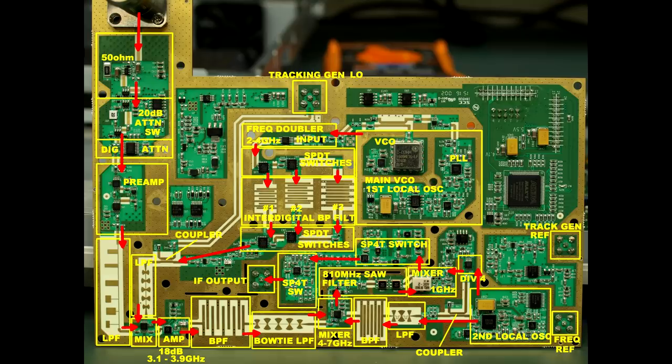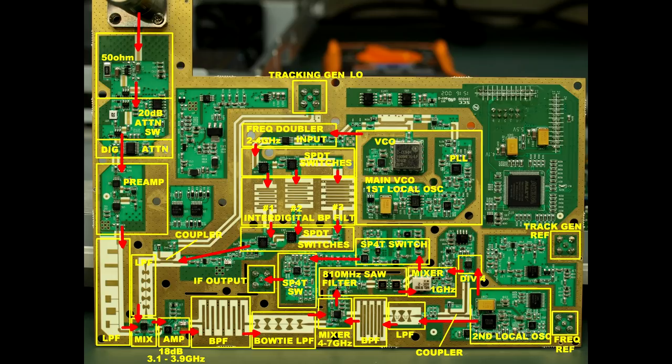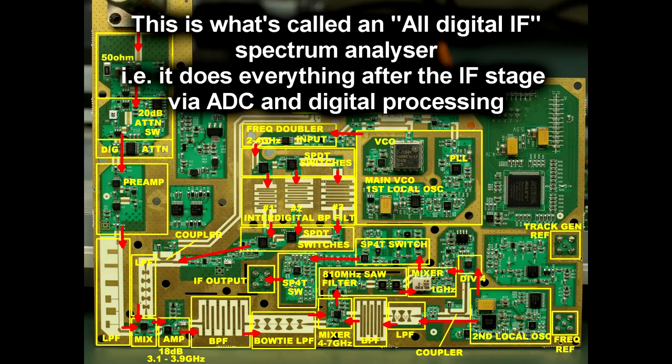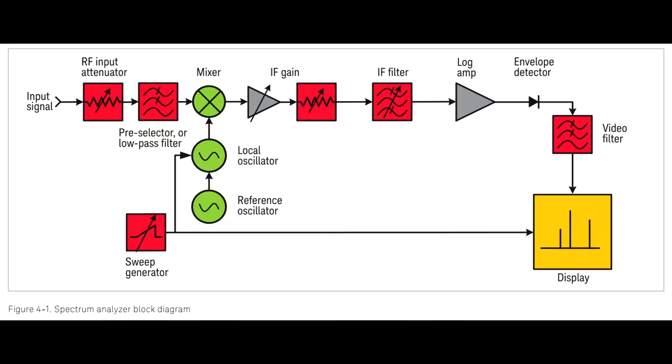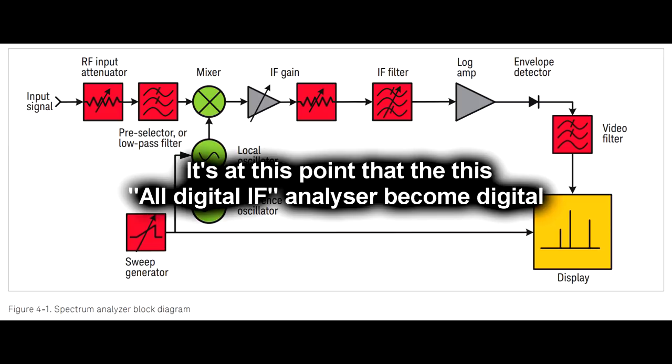Now that's all bread and butter stuff, but look at all these other blocks in here, and this is the complex operation of a spectrum analyzer. Not all spectrum analyzers operate the same, but they use very similar techniques. So we've looked at basically just one block here, the RF input attenuator. Now we expect to see a low pass filter in here, and then that goes into a mixer, which uses a local oscillator, mixes the two signals together, generates a higher frequency called the intermediate frequency, and then we expect to see a gain stage there, an attenuator, that IF thing goes into an IF filter, and then it goes into a log amp, envelope detector, video filter, and display.